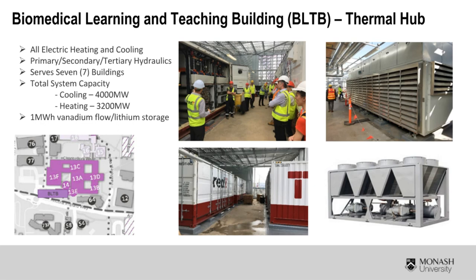The system has primary, secondary, and tertiary hydraulics, which relates to the pumps and what level they go down to within each building. The hub is going to serve seven buildings in the precinct and has a total capacity of 4,000 kilowatts cooling and 3,200 kilowatts heating. In the original business case for this precinct, we did have some storage in the basement, but the civil engineering costs for the tanks made us look at batteries instead. So we put in a 1 megawatt vanadium flow energy storage system by Redflow.